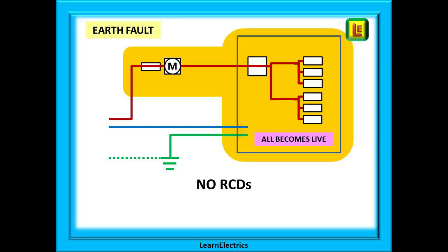But what could go wrong? Imagine a metal consumer unit with no RCDs installed, relying on MCBs or fuses alone for protection. An earth fault develops and the fault current flows along the earth conductor, but as we have just calculated, only 2.3 amps flows because of the high soil resistance. All exposed metalwork that has a connection to the earth bar will become energized at 230 volts until the fuse blows or the breaker trips — but it won't trip, because at best it's a 6 amp breaker or at worst perhaps a 32 amp device. All the metalwork in the property will be energized and the circuit remains live. Touch the metalwork and it's going to hurt.